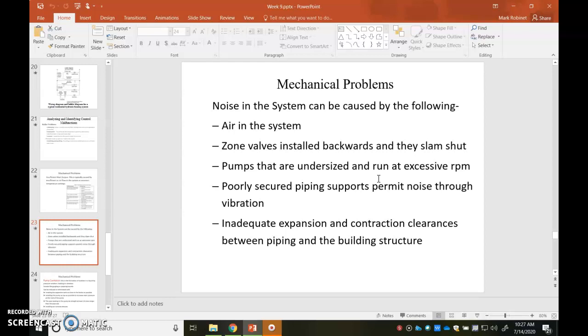Remember, any kind of noise on a boiler system reverberates through the entire system. It's kind of like pounding on ductwork, right? You'll hear it throughout the entire house. Poorly secured piping supports permit noise through vibration, and inadequate expansion and contraction clearances between piping and building structure. If you screw the copper for the water that goes through it directly to a joist, that copper is going to want to expand and contract based on if it's hot water or cold water going through the piping, and will make creaking noises. I had them in my old house. There was no way I could get to them. I just had to live with it. But on a new installation, that's something you'll want to take a good look at.